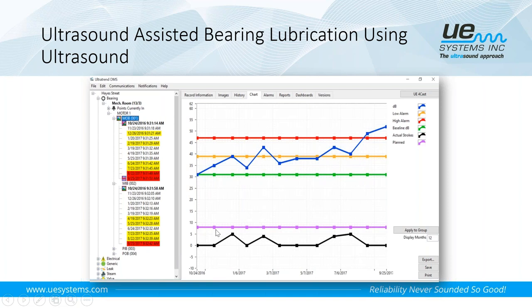And then the bottom graph is showing us the planned number of pumps of grease compared to what we actually put. And anything you want to see on this chart can be selected in the history tab. So if you didn't want to see the number of pumps of grease, you could just go into the history tab, take those off the chart, move them over to the right, and then go back to the chart. And then the only thing you would see would be your decibel level readings. But anything you want to see on the chart, you would choose that in the history tab.